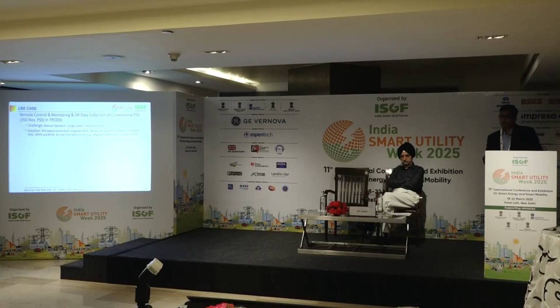Now, the solution we have provided is RTU-based automation, which integrates BCPU, relays, DC system, fire detection system, TMU, NIFPS, and MFM for real-time data monitoring, with integration to the control center SCADA. Benefits: we have remote control and real-time monitoring of the PSS, unmanning of PSS, and cost saving in operation, because earlier we needed to deploy an operation engineer in all 385 substations, which is very costly for us. We have made many substations unmanned, gradually we will make it 100%, and these operation engineers are being utilized for other purposes. Also faster restoration, improvement in AT&C losses, improvement in reliability indices SAIDI, SAIFI, and remote maintenance and configuration, and customer delight.